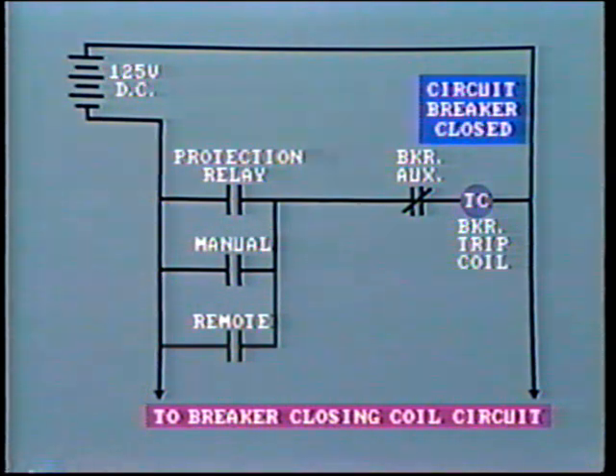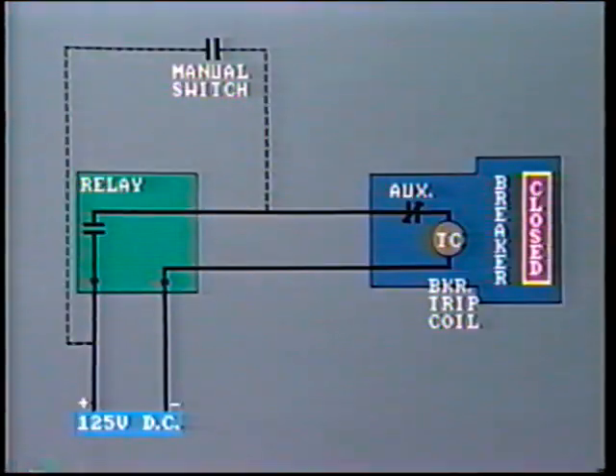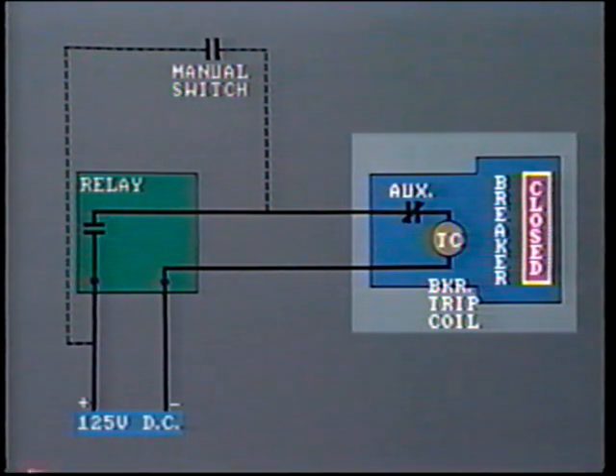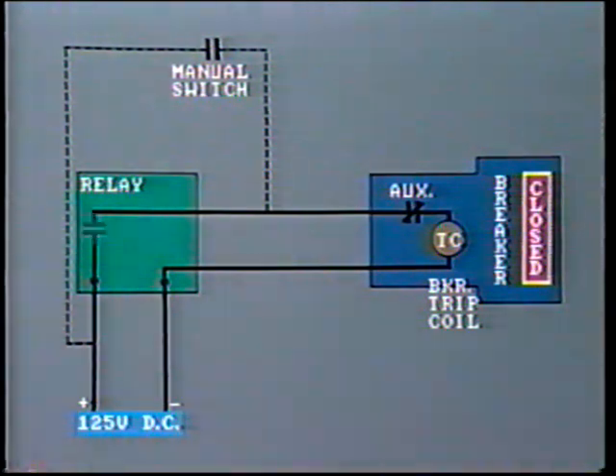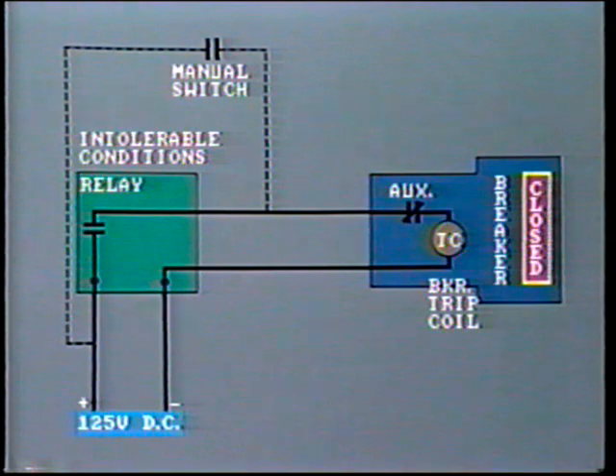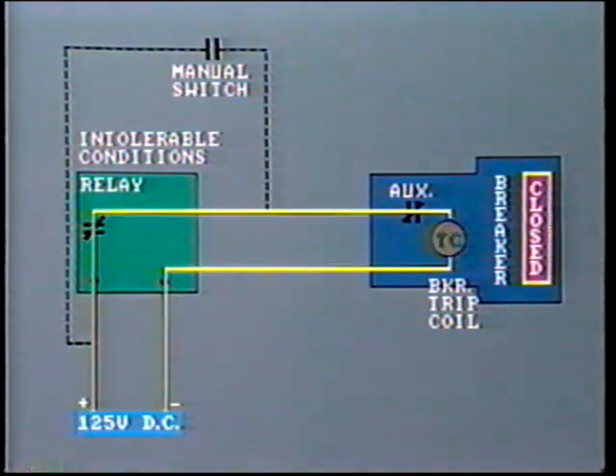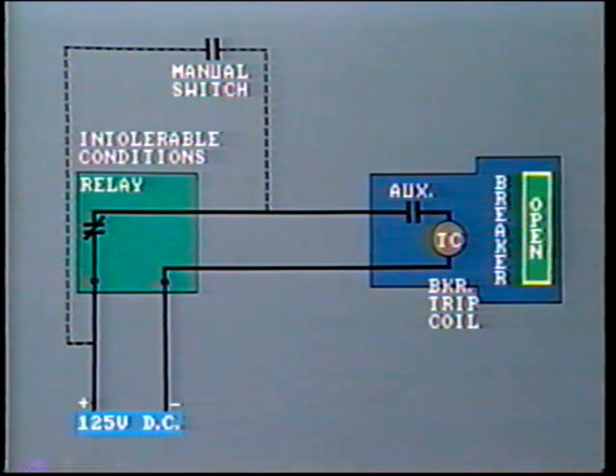In practice, there may be other parallel contacts which can open the breaker. Remember, the circuit breaker tripping coil and its auxiliary contacts are normally located at the circuit breaker inside the cabinet. This is probably in the switch yard, some distance away from the relay panel. However, relay operating contacts are located inside the relay. The manual switching contacts are normally located on the control panel. Now, when the relay operates due to sensing intolerable conditions, the relay contacts will close, and this now energizes the breaker tripping coil. This in turn causes the breaker to open and also causes the auxiliary contact to open, so breaking the DC tripping circuit.